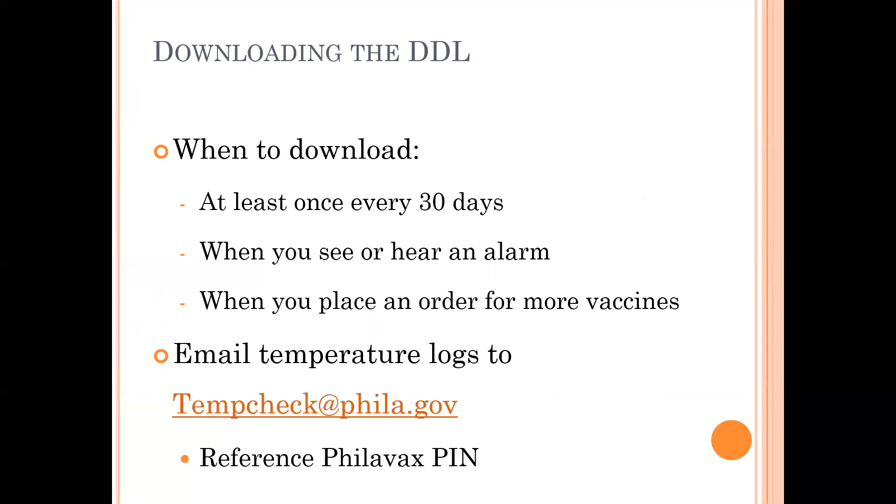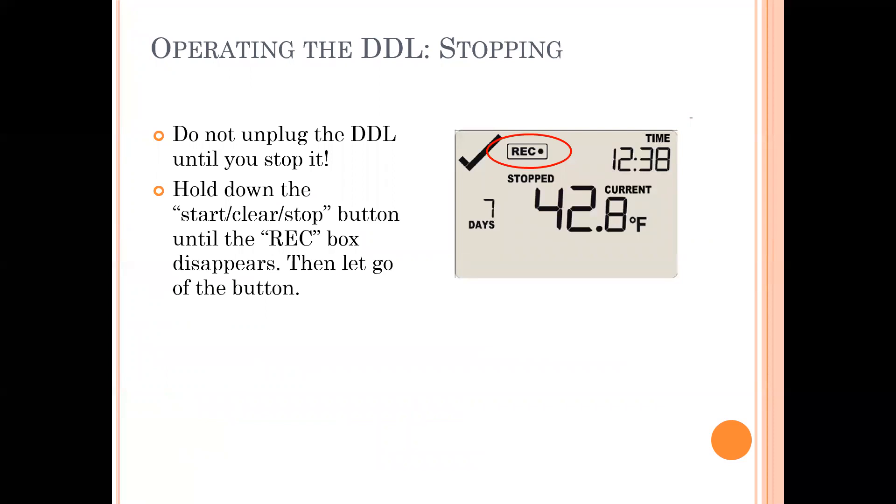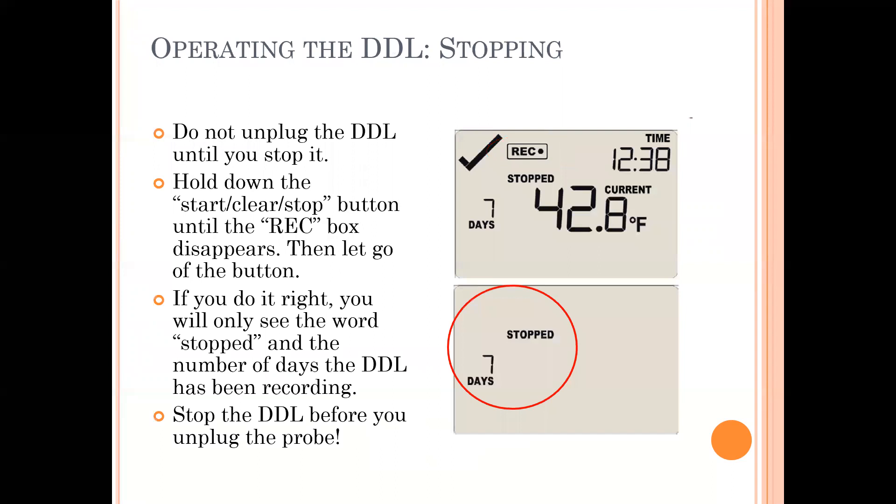Now let's go through the process of downloading your DDL. If you have a refrigerator and a freezer, they should already have DDLs monitoring them. The first thing you're going to want to do is stop the DDL. To do this, turn it off before you unplug the probe. Simply hold down that start/clear/stop button for two seconds. You will see the record box disappear and the words 'stopped' appear. When that happens, let go and it will stop. If it cycles back to the temperature display, you didn't do it right — try it one more time.